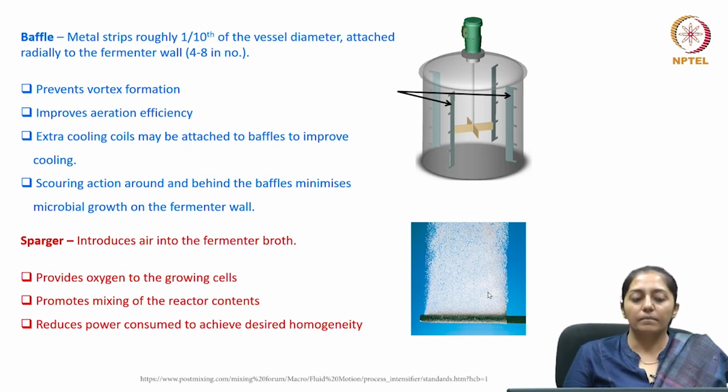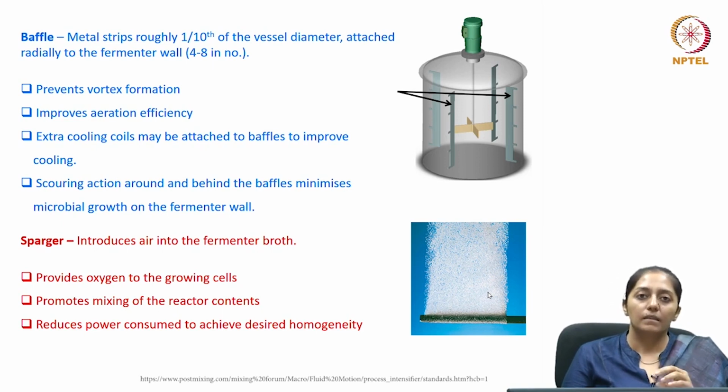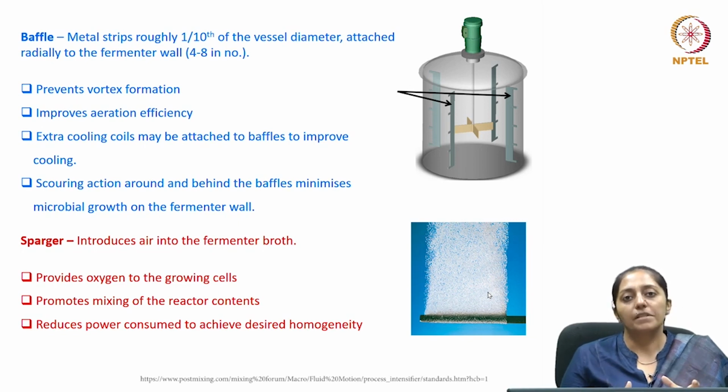Baffles, as I said earlier, are nothing but stainless steel strips, roughly 1/10 of the vessel diameter, attached radially to the fermenter walls. Their function is the prevention of vortex formation, because if a vortex forms, it will lead to dead zones at the corners of the reactor. To avoid the dead zones, which can hamper uniform mixing and a uniform environment inside the reactor, baffles are placed. They also facilitate improved aeration efficiency.